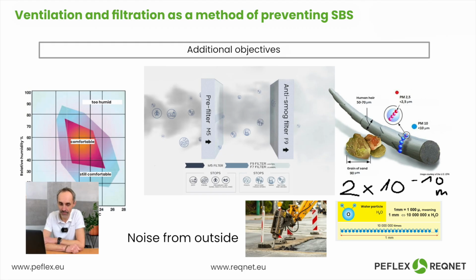And the optimal range for comfort, right? It concerns thermal comfort. Thermal comfort consists of three parameters. That's temperature, humidity, and the air velocity at which air flows through the building. So the optimal comfort range in terms of temperature is 18 to 22 degrees. In terms of humidity, it's 40 to 60%. And as for air velocity, the airspeed should be about 0.2 meters per second in the area where people are present.